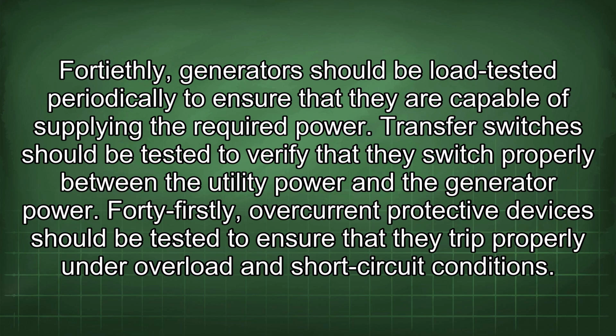40thly, generators should be load tested periodically to ensure that they are capable of supplying the required power. Transfer switches should be tested to verify that they switch properly between the utility power and the generator power. 41stly, overcurrent protective devices should be tested to ensure that they trip properly under overload and short circuit conditions.